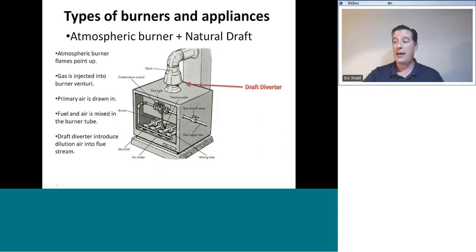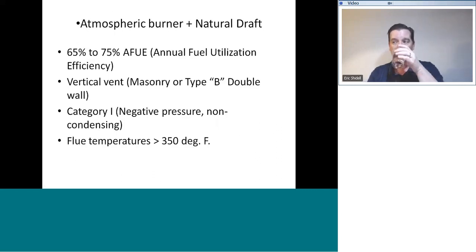So if you see that, get your carbon monoxide tester out and see if you're getting flue products right in that area, and you probably will be. Now go open a window or the front door of the house and open all the doors, and you will see, lo and behold, sure enough, that went away, because now we are drawing air in. Some of the features of the atmospheric burner plus the natural draft is efficiencies are generally pretty low. We're looking at annual fuel utilization efficiencies of 65 to 75%, AFUE. That might be on the test.